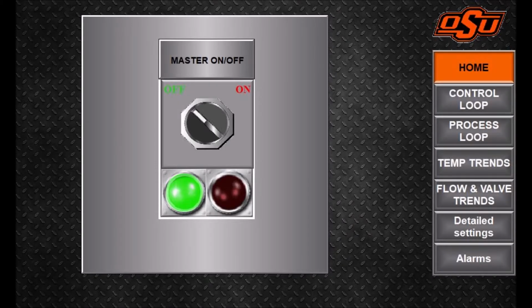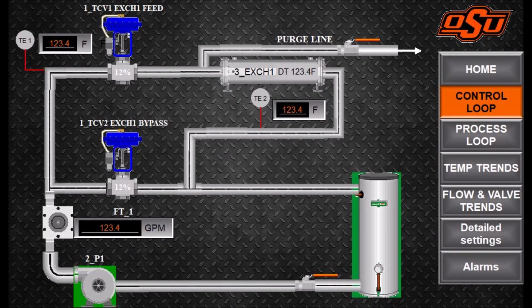Here is our HMI screen. On the home screen, the operator is able to turn on or off the entire system. The screen selector on the right allows the operator to choose which screen they will view. In the control loop screen, a visual representation of the control loop is shown. The water heater is used to heat the fluid as the pump pushes that fluid through the heat exchange feed valve or the exchange bypass valve. When equipment is in use, it is shown with a red background and green when it is off. The flow rate is shown in gallons per minute beside the flow meters.